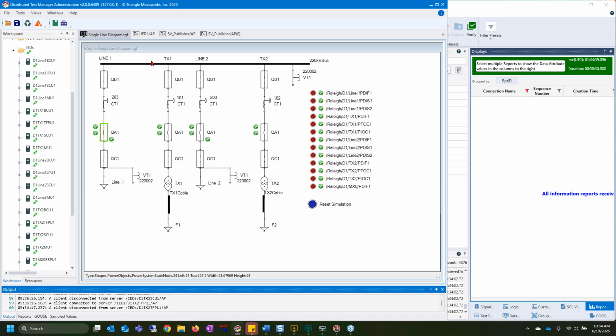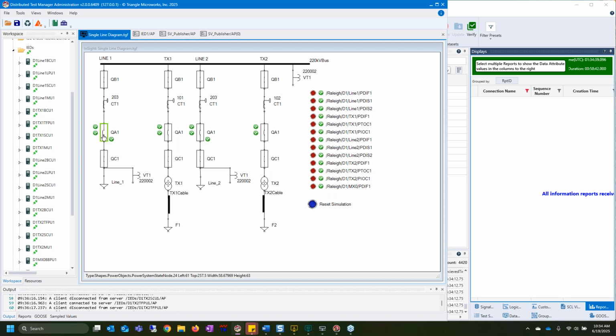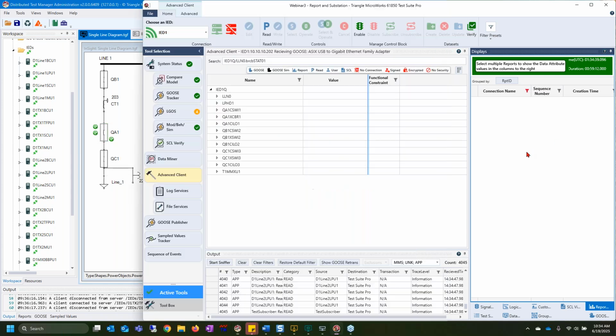So with all of these values, you can see voltages on the voltage lines here. The currents can be seen on the transformers here. And if I simply open a breaker, we can see this current dropping to 0. And all of that information is then being fed over to the devices seen over on the left. Of course, as Jackson mentioned, data changes will trigger a change within the database, the data attributes, and will cause events to occur. So things like reports or GOOSE messages will be sent out. The second software we'll be looking at today is the Test Suite Pro tool, and that can be seen here on the right. Our Test Suite Pro tool is our client tool for testing and diagnosing of events and occurrences within your system.